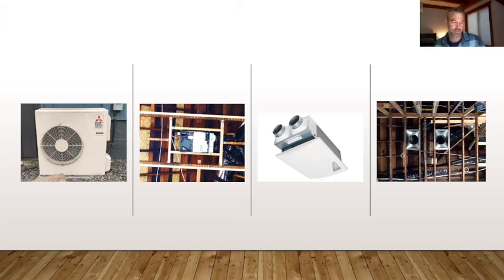So Richard, what I think you're referring to is the through wall vent, which is a passive system and fulfills the requirement needed for a lot of houses. So there are multiple options for indoor air quality and making sure that when you super seal a home, you don't have a negative air pressure happening when you're exhausting different rooms. So the through wall units that I think you're referring to keep that air balance in place. And it's just a passive system so that as air gets pulled out of the space and vented, fresh air can come in through the wall.